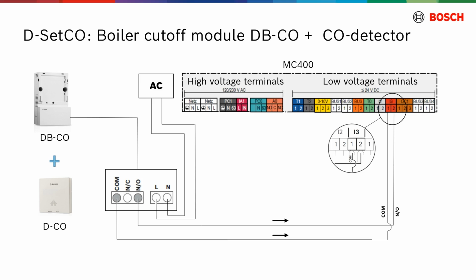The DBCO is also autonomously connected to the power supply, AC. In case of a critical CO level, the cascade will be shut down. The cascades will not be completely off power. They will restart only when the critical CO level has been underreached. Therefore, the CO detector must be connected to the MC400 Cascade module.